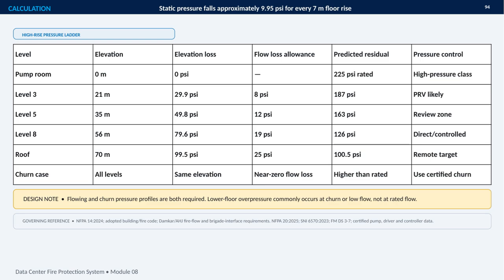The design challenge is balancing adequate pressure at the highest remote point with overpressure protection on the lower floors. The table also includes allowances for flow loss, which increase with elevation and system reach. That is why pressure control may require pressure-reducing valves, zone review, or direct control, depending on the level. We also need to evaluate both rated flow and churn conditions.